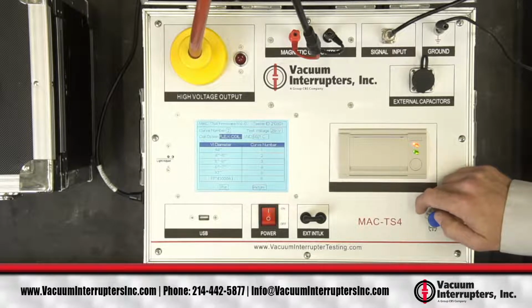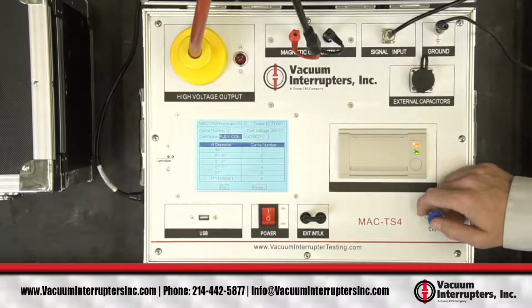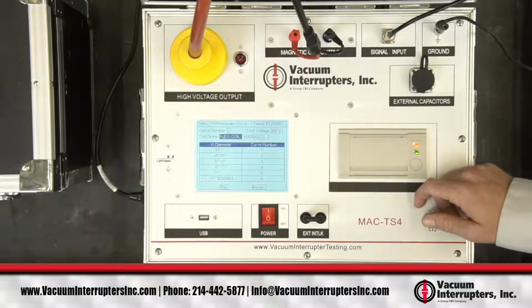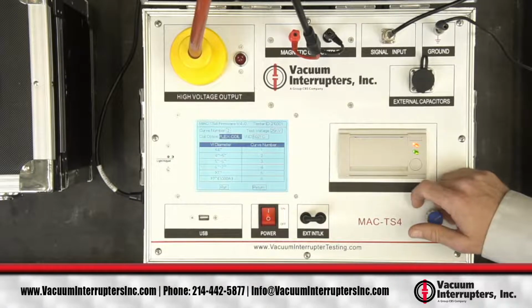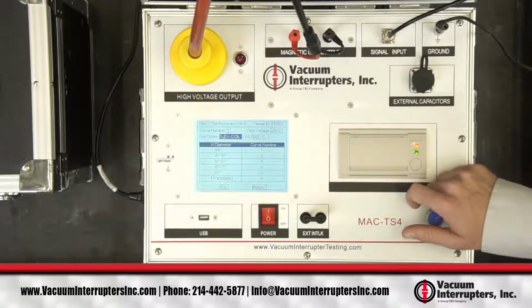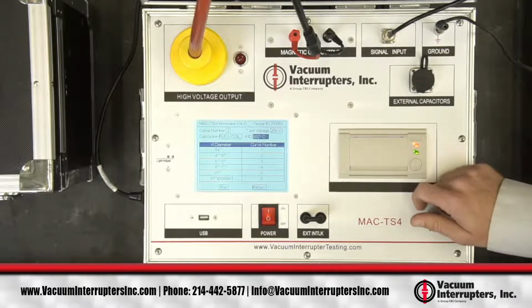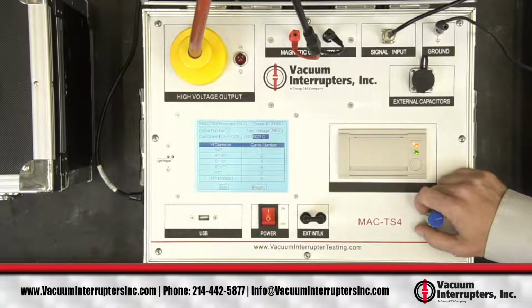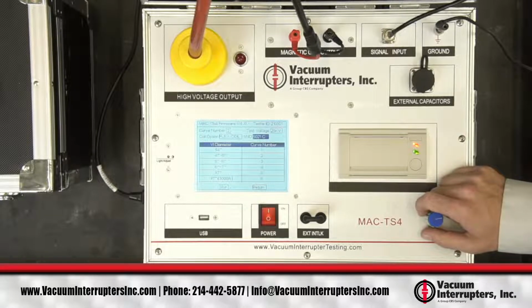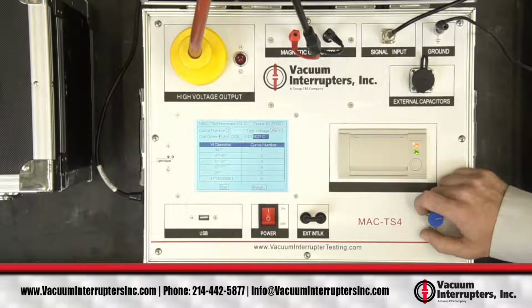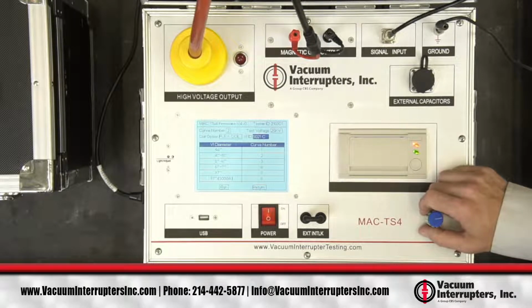Then you want to select your coil. So here we're using a flex coil. There are other coil options. If you had the vacuum interrupter removed, then we have some fixed coils that you could test in. And then you have the option of putting in a VIID. So this is just a way to recall this data and have a reference. So it could be the breaker type and the phase, or the VI serial number, whatever helps you to identify the test results and the vacuum interrupter.